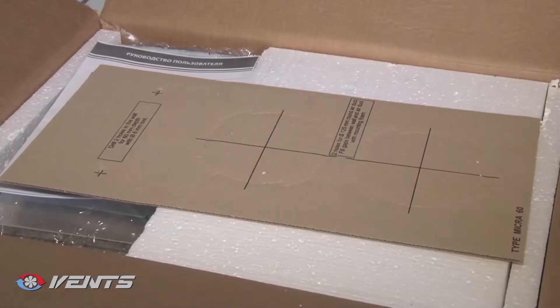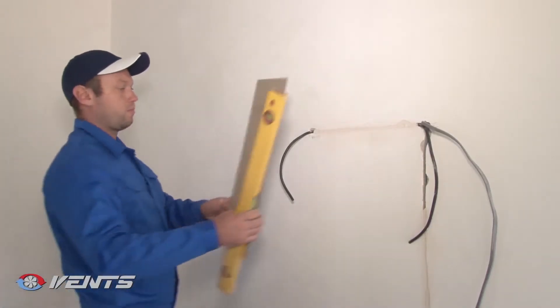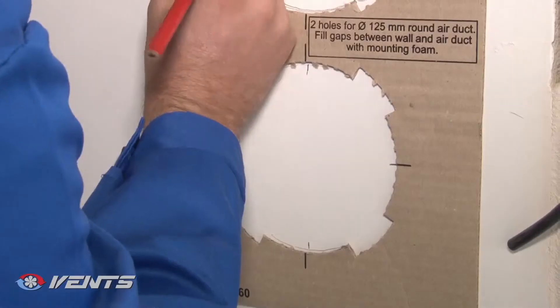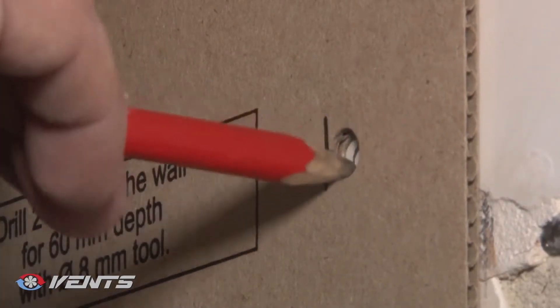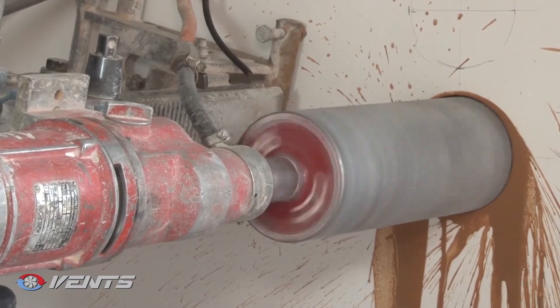The Micra 60 air handling unit features simple mounting. You will need the supplied mounting template, and remember to purchase two air ducts of required length and 125 mm diameter. Mark the holes for the air ducts and fastening holes using the mounting template. Then remove the mounting template and drill the through holes.